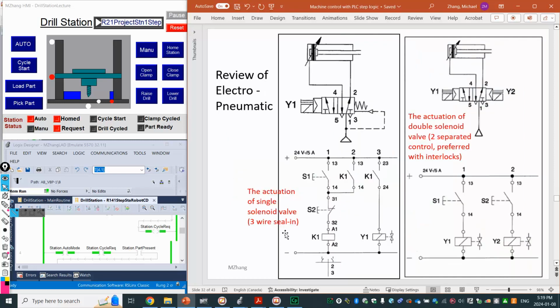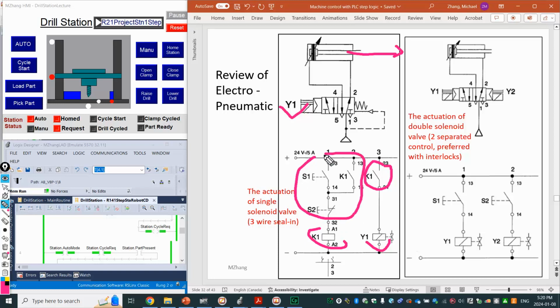So with the valve control, with these two different types, again a little bit of review from the electro pneumatic. If it's a single solenoid valve, for example on this circuit, if you want to maintain the cylinder at the extended position, you have to energize Y1, right? Y1 on this circuit is energized by the control relay K1 normally open. That's the coil, and then look at the control here. That's typical 3-wire control, right? That's what we learned with the seal-in. The reason for that is you have to bypass this start signal, otherwise this cylinder will not stay at the extended position, right? You have to keep this Y1 energized all the time, right? So that is the single solenoid valve.